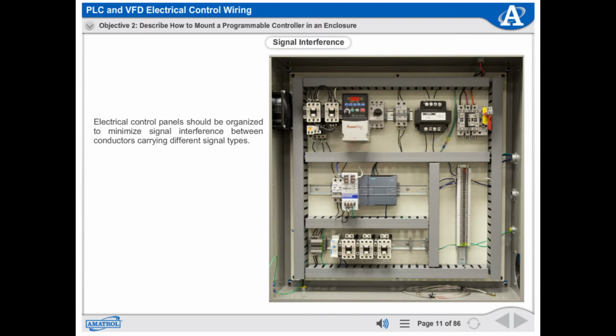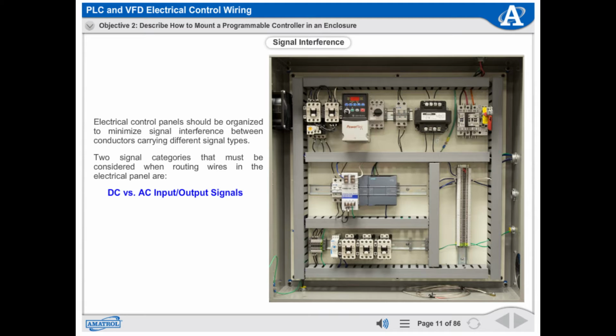Electrical control panels should be organized to minimize signal interference between conductors carrying different signal types. Two signal categories that must be considered when routing wires in the electrical panel are DC versus AC input-output signals, and power signals versus control signals.